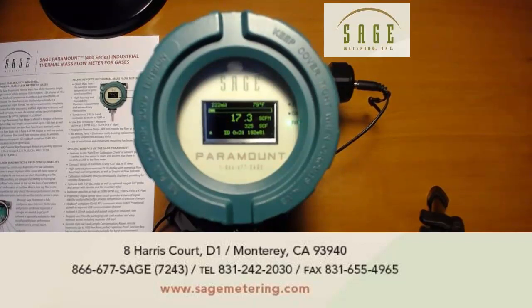The Paramount has a Division II rating, has an explosion-proof enclosure, and a separate rear compartment that is totally independent from the front side of the meter. The standard outputs of the meter are 4 to 20 milliamps, proportional to flow rate, pulsed outputs of consumption, as well as Modbus communications. BACnet communication is optional, and HART is optional.